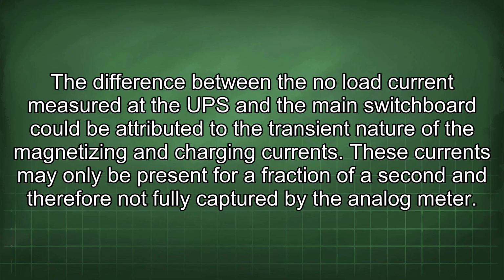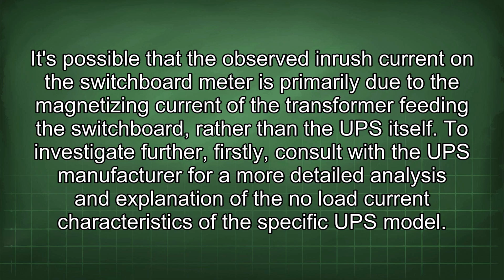The difference between the no-load current measured at the UPS and the main switchboard could be attributed to the transient nature of the magnetizing and charging currents. These currents may only be present for a fraction of a second and therefore not fully captured by the analog meter. It's possible that the observed inrush current on the switchboard meter is primarily due to the magnetizing current of the transformer feeding the switchboard, rather than the UPS itself.